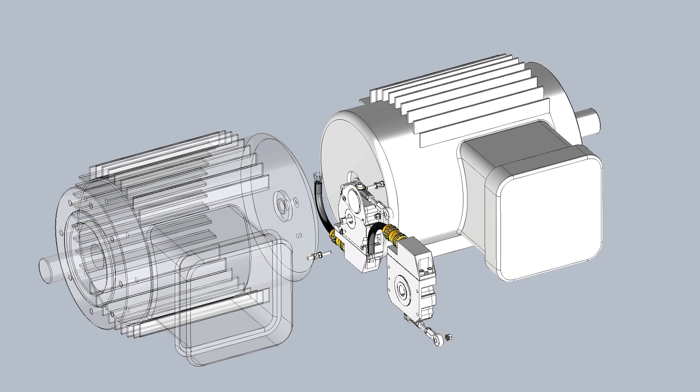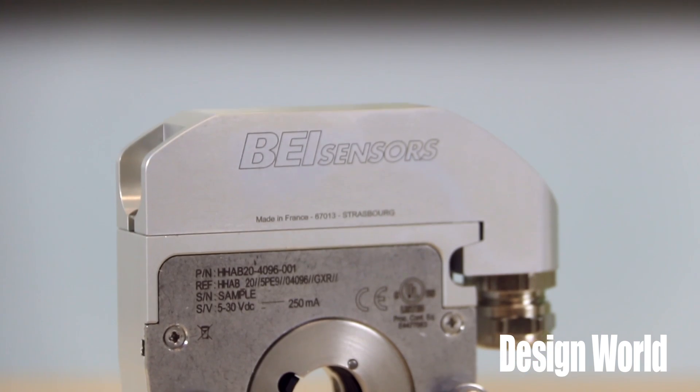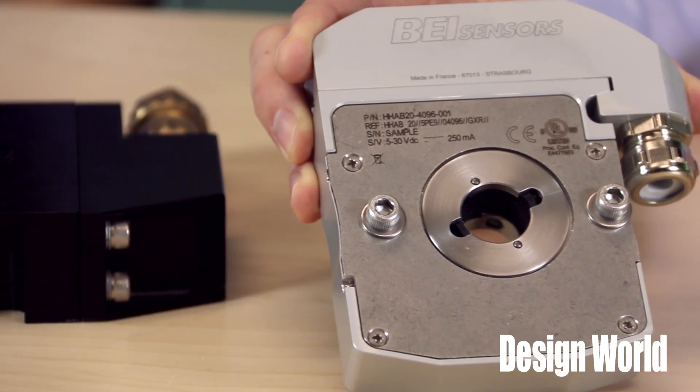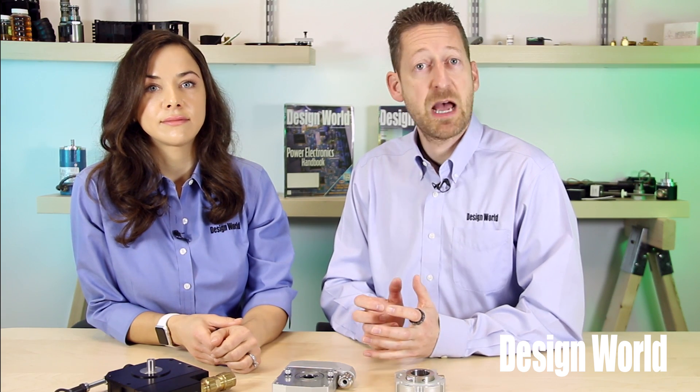Just consider the quick installation and dismantling of two hollow-shaft LP series encoders in a back-to-back motor installation — say between industrial-duty motor flanges and fans or in back-to-back motor mountings. A programmable option lets users select any resolution from 1 to 10,000 ppr for versatility and to reduce lead time and stocking costs. The terminal box option allows pre-wiring to prevent wiring errors, and it comes with standard enhanced electronics for over-voltage protection, which prevents encoder failure and downtime. The electronic design with the terminal blocks contains robust output drivers that allow for long cable runs with no loss of signal.